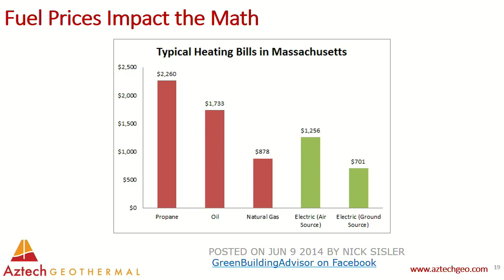You've got electric air source heat pumps, and there's lots of information about that. We install and monitor those as well, and I am very curious about NetZero Village and trying to get data from there, just to see how they really perform. They use about twice as much energy as a ground source system seasonally if you compare like technologies. So if you have a variable speed ground source and a variable speed air source, the ground source usually uses about half the amount of electricity in the winter, and about half in the summer, and in particular at the peak, which is the most important thing to the state.